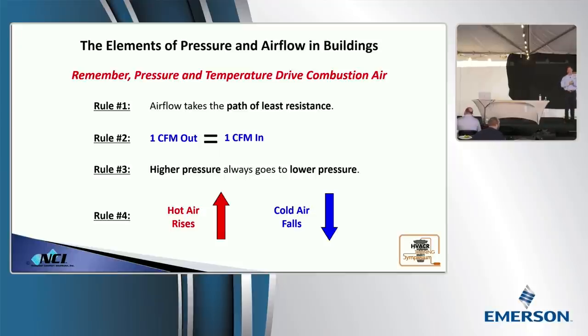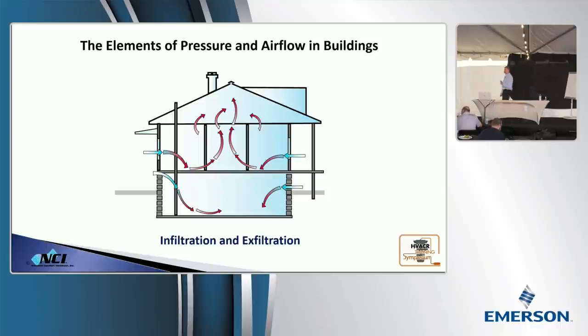Rule number two, any air that's leaving a building is trying to come back in from someplace else. 1 CFM out, 1 CFM in. That's the exhaust fans that you guys were talking about, kitchen exhaust hoods. That's the principle that they operate off of. The third rule, higher pressure, lower pressure. These are things that we know, but we're going to plug them into combustion air. And then rule number four, although it's super simplified, hot air rises, cooler air falls and displaces it. We're going to look at how this ties in to combustion air ducts, because as those rules are going on, they create both infiltration and exfiltration.